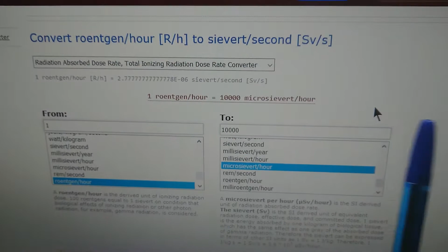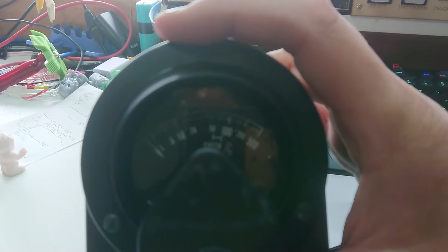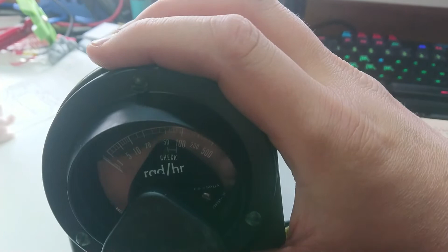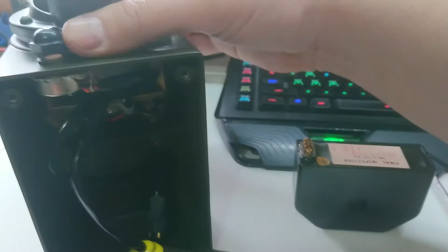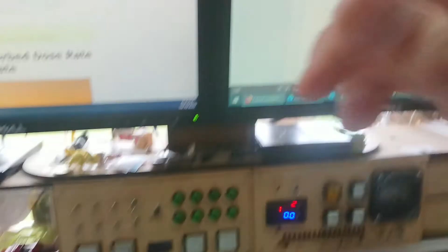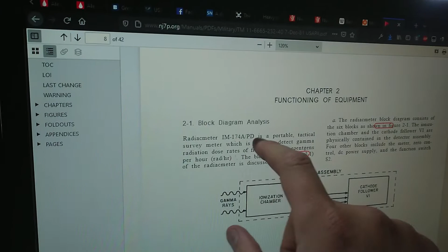But yeah, 1 Roentgen, I wouldn't want to be hanging around that for very long at all, probably a few minutes at most. So certainly not in a concentrated beam. Anyway, that just gives you some idea of the scale of this unit. In fact, actually we can go over and have a look at the front panel of it to understand the exact scale. That's a little bit off balanced at the moment. So we are, yeah, a minimum reading is 1 Roentgen per hour. Well, this is rads per hour, so I might just check that Roentgens and rads are correct, although it is saying Roentgens in the manual for this exact unit, so I'm pretty sure Roentgens and rads are pretty close.